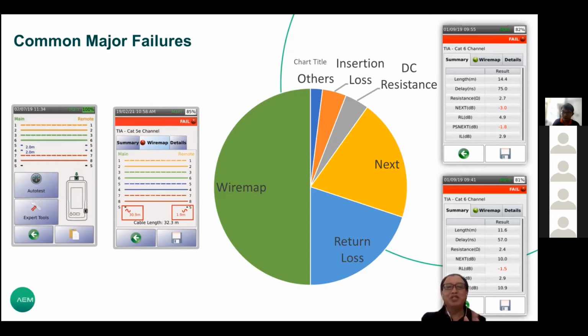Another failure could be shielding. Sometimes you have a shielded cable. Now, shielded cable is actually more common now than unshielded. So sometimes people do not know how to terminate the shield. There is foil shield, and there is also the drain wire inside the cable that you need to ground properly to close the loop. If you don't do the proper grounding, you have an open shield.